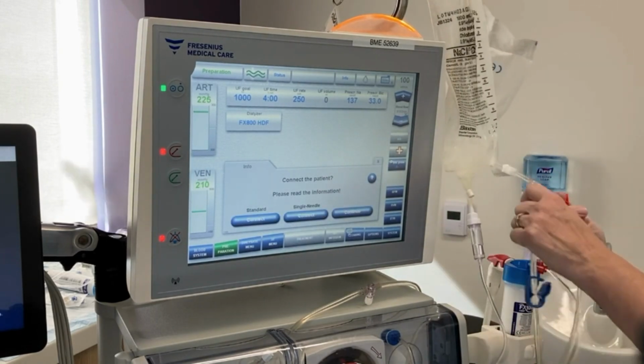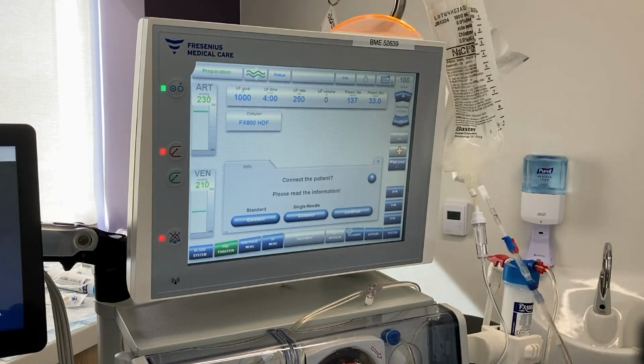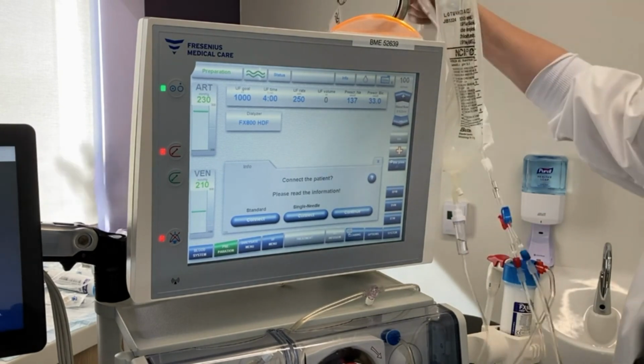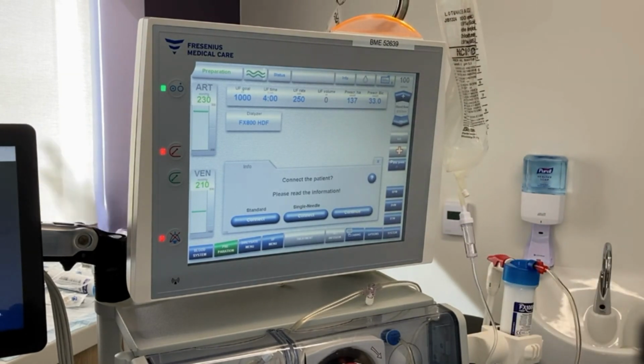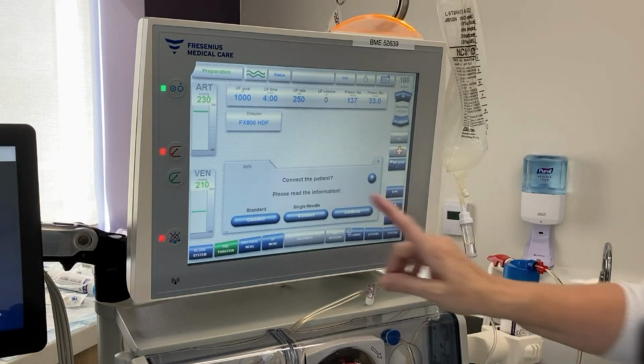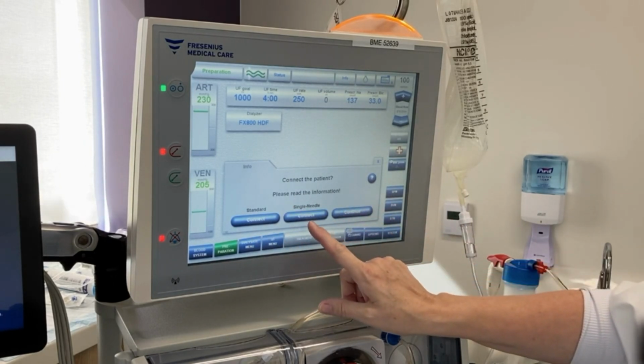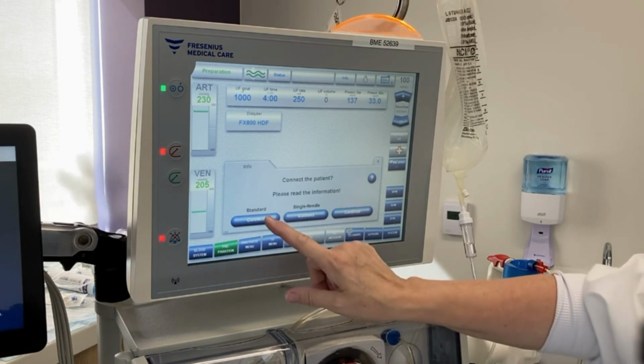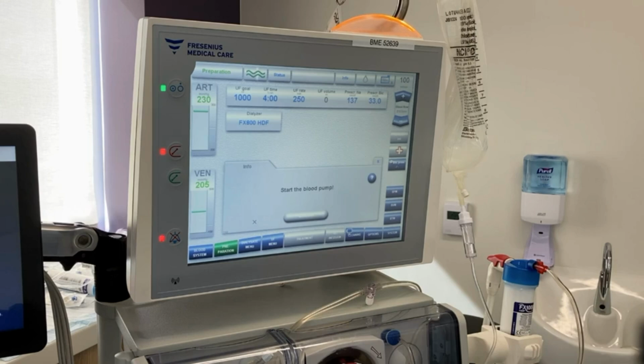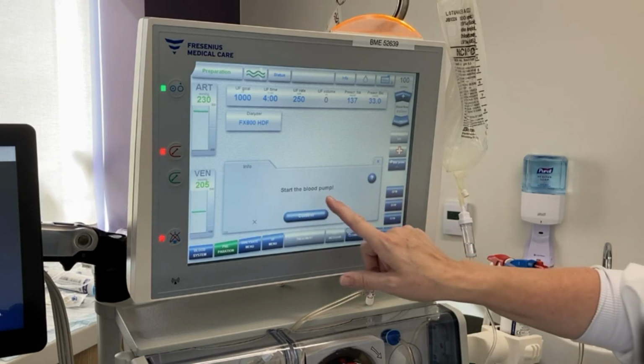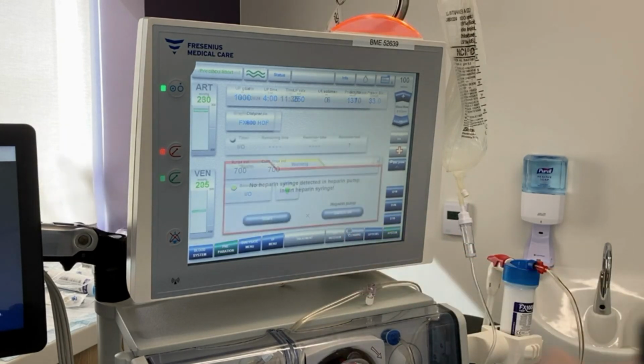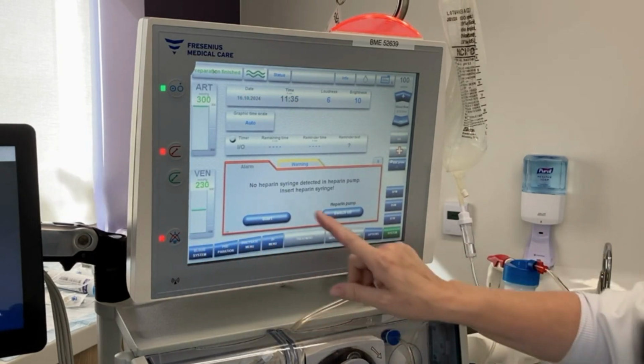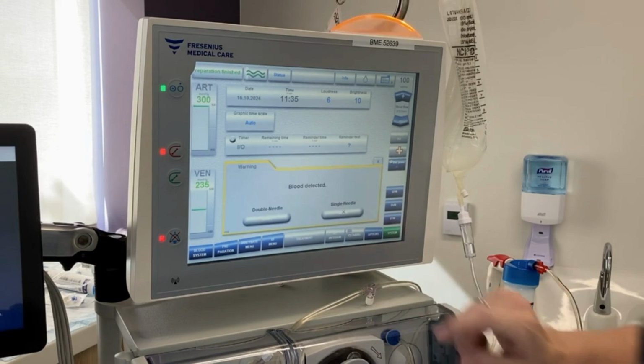So we clamp, and connect to the patient. And we've got the option here that we could either do single needle or standard connect. And we're actually just going to choose standard connect. So it says here to start the blood pump. So once it sees blood, we're not using heparin today, so I'm going to switch the heparin off.